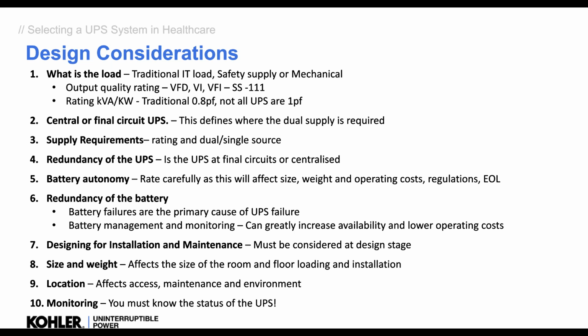Supply requirements: what's the rating? Is it dual? Is it single? That's the supply to the UPS. And then there's the redundancy of the UPS. Are we going to have redundancy in the fact that we've got 2 central UPSs, or a centralized UPS with N+1 in it? That's all the kind of thing you have to talk with the stakeholders about, what type of redundancy you need. The autonomy of the battery is critical. We need to understand the regulations and make sure we have the right type of battery, sized for end of life, things like that.